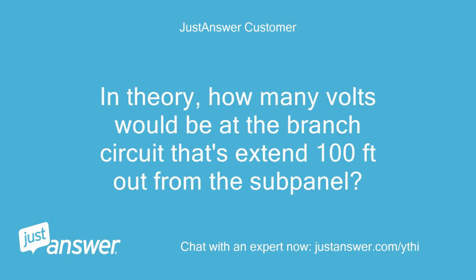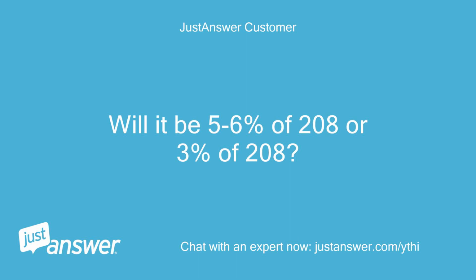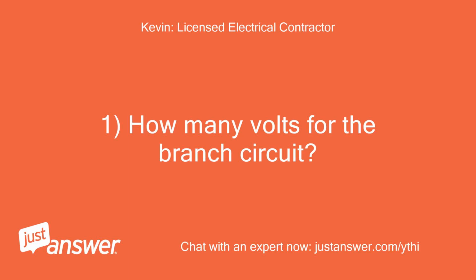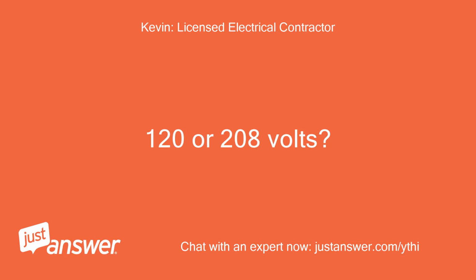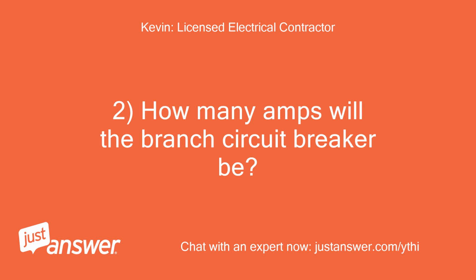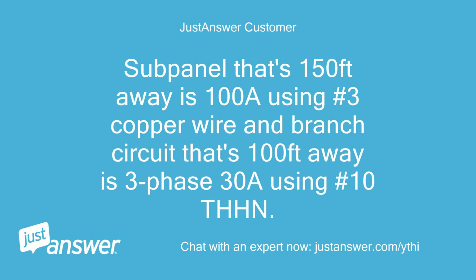In theory, how many volts would be at the branch circuit that extends 100 feet out from the subpanel? Will it be 5 to 6% of 208 or 3% of 208? 1. How many volts for the branch circuit? 120 or 208 volts? 2. How many amps will the branch circuit breaker be? The subpanel that's 150 feet away is 100A using number 3 copper wire, and the branch circuit that's 100 feet away is 3-phase 30A using number 10 THHN.